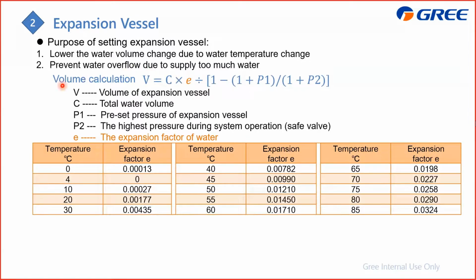And also another calculation: based on this formula, we can get V, which is the volume of the expansion vessel. C here is the total water volume, and after you install the water system, you already know this value. E is the expansion factor of the water. This is based on the water you use, so this value is also different. You can get it from this table. As for P1 and P2, they are the setting pressures of the expansion vessel.